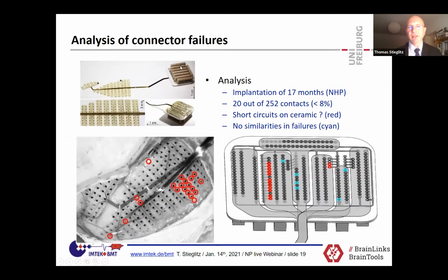And the reason for that is, you might know those Omnetics connectors. They are really tight. And if you have to put your cable on and off every day or every second day, you have to wiggle it on. And by wiggling around, the forces will be transferred to your solder points and to the underlying epoxy. And then the epoxy gets a little bit loose, the water creeps in, the water condenses, a little bit of salt is drawn by diffusion through that, and then you just have short circuits and see the same signal on a complete row of your connector. And the more channels you have, the higher the probability that you see those things.